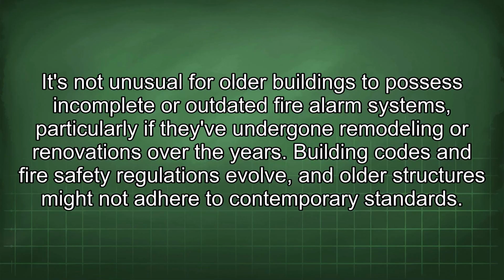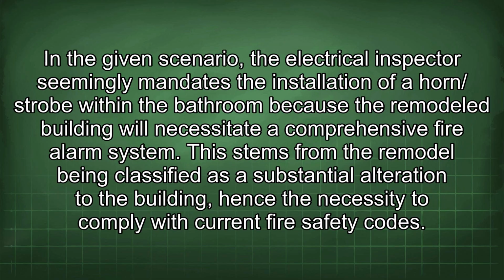It's not unusual for older buildings to possess incomplete or outdated fire alarm systems, particularly if they've undergone remodeling or renovations over the years. Building codes and fire safety regulations evolve, and older structures might not adhere to contemporary standards. In a given scenario, the electrical inspector seemingly mandates the installation of a horn/strobe within the bathroom because the remodeled building will necessitate a comprehensive fire alarm system.